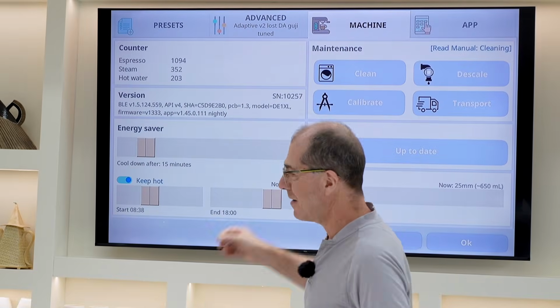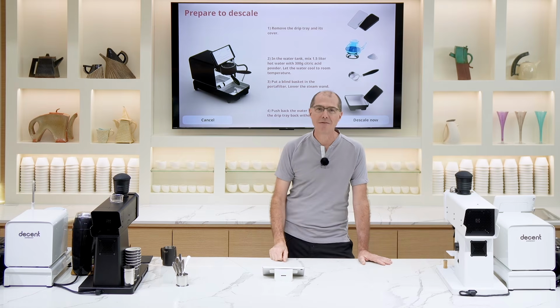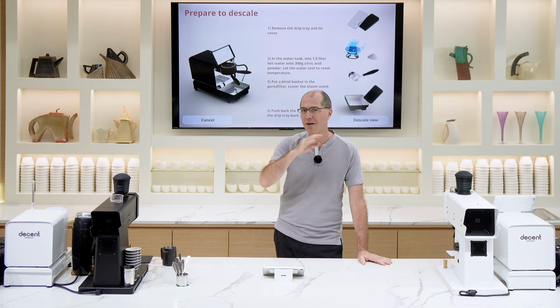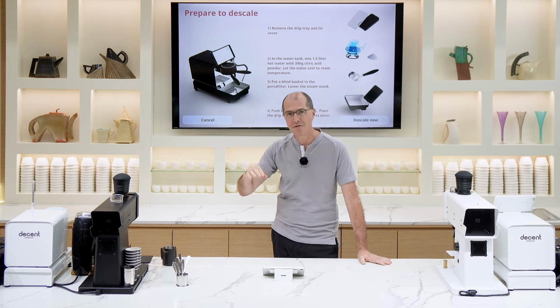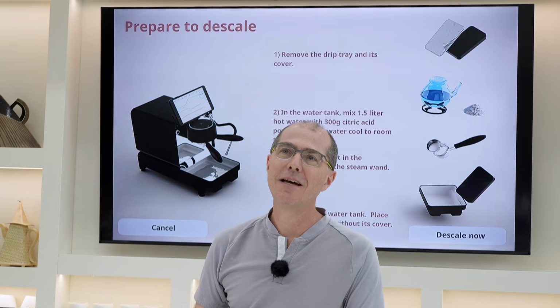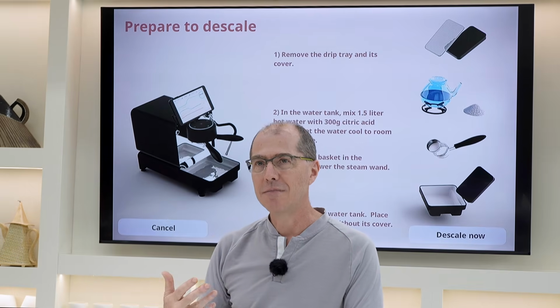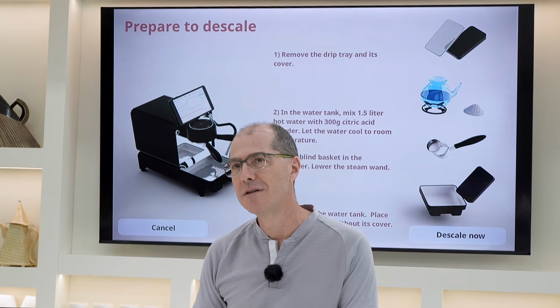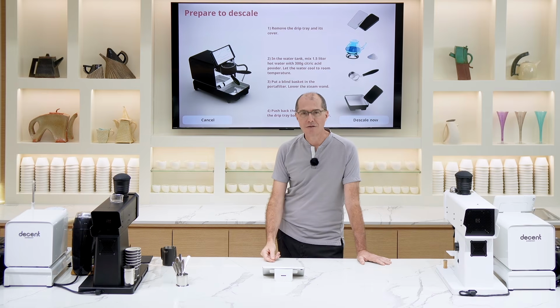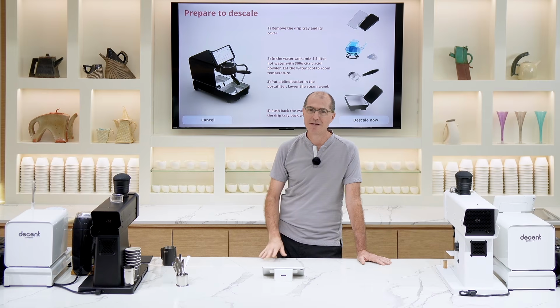The descale button is a little bit different. You'll want to descale, especially if you find that steam is starting to oscillate. It goes faster and then slower, faster, slower. That's a telltale sign that you've got some calcium building up inside your tubes. If you're using extremely low calcium water, you won't need to descale very often, if at all, which is why low calcium water is recommended.